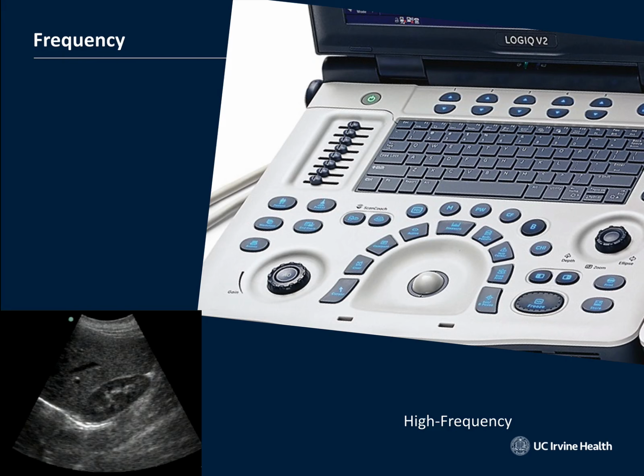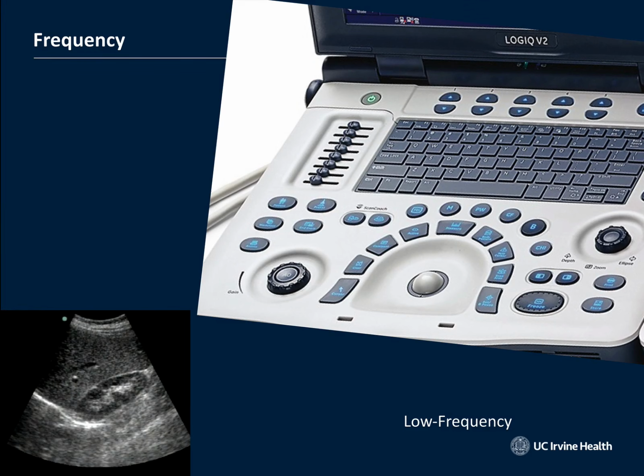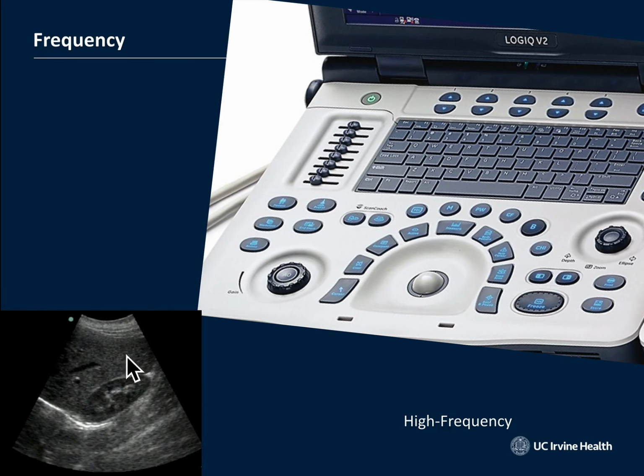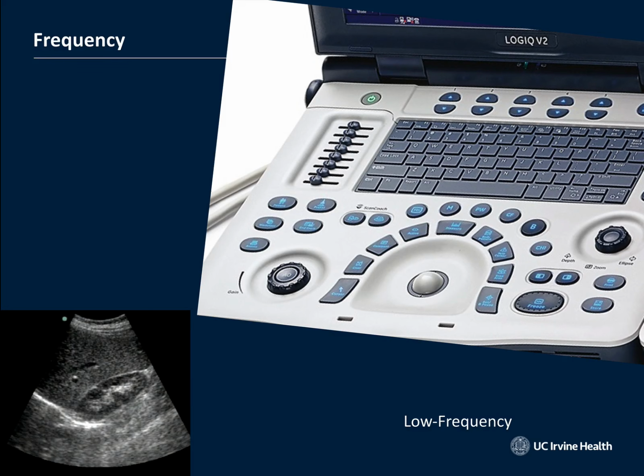When you turn up the frequency to that, say, 5 megahertz range, now the dots got a little bit tighter, a little bit closer together. The sound doesn't penetrate as well, but the image is more resolute. And as you bump it down to that lowest frequency setting, say 1 megahertz, now the dots splay away from each other, and it's, I don't want to say the word grainy, but it's a little grainier than the other images. So I'll go back to the previous resolution, high frequency mode here, like 5 megahertz. Dots are very close together, and then the other extreme down here to the lower frequency mode.